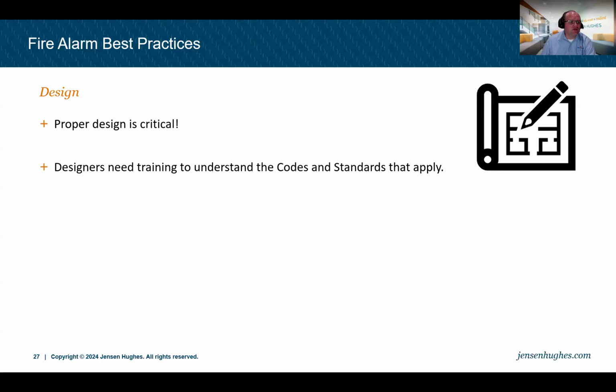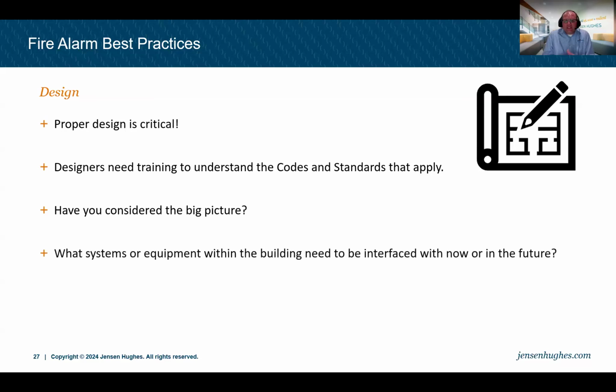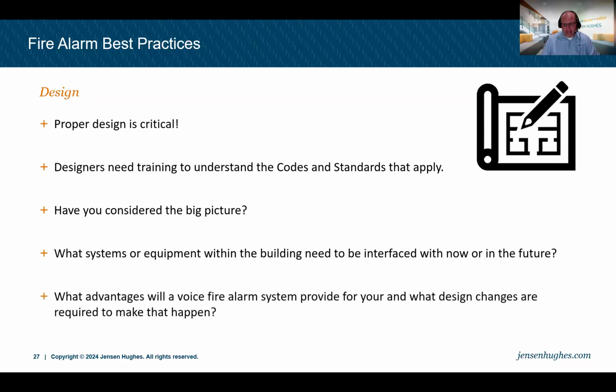If you use third-party designers who agree to design the system, they need to make sure that they are qualified. Make sure that they've considered the big picture. Have they considered all the other equipment in the building that needs to be noted? And you'll want to check their credentials in that. What systems or equipment within the building may need to be interfaced with now or in the future that could be designed into the system now? Because you have to be able to address critical interconnected emergency control equipment, wiring to fans, dampers, smoke control equipment, elevators, and the like. And what advantages will a voice fire alarm system provide for you, and what design changes are required to make that happen, so that we can communicate with people rather than just activating a bell or a horn, which really doesn't tell anyone anything.